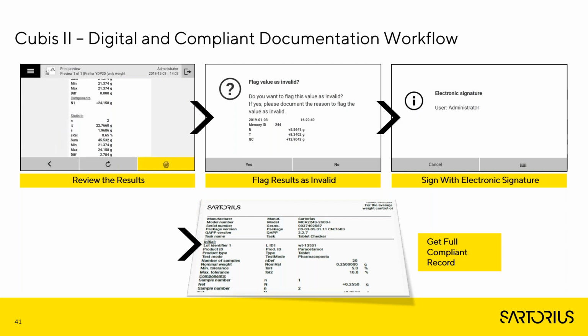In this slide, I will give you an example of a digital and compliant paperless documentation workflow and how this can look. We will use the Sartorius Cubis II balance, where we have implemented this kind of workflow directly on the balance. First, you need a feature to review results before you create a report. This can be done directly on the balance. In case there was an error during the measurement and you need to mark the wrong value, you can do it directly on the balance by flagging such a result as invalid and writing your comment or cause on the balance touchscreen. Then, when you have reviewed your results and made the corrections, you can directly sign it on the balance with your electronic signature.